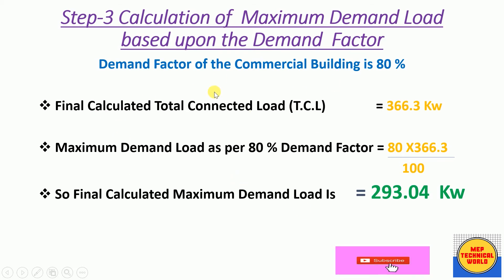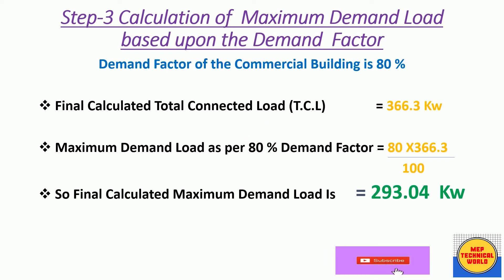Why do we calculate maximum demand load? In a hotel or any other building, not all loads are connected to the power supply 24 hours a day. During daytime, lights may be switched off, and at night some machines are also turned off. So all loads are not connected simultaneously at any given time. Calculating the maximum demand load helps us determine the real size of the diesel generator. If we sized the DG based on total connected load, the DG size and cost would be unnecessarily increased.